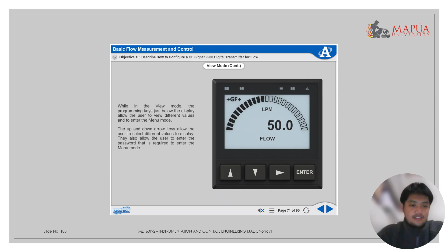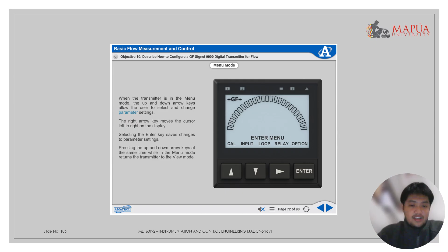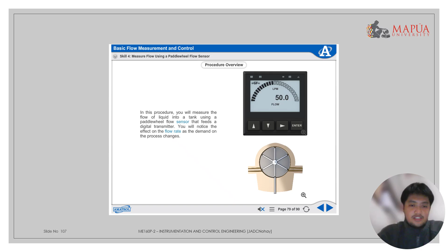When the transmitter is in the menu mode, the up and down arrow keys allow the user to select and change parameter settings. The right arrow key moves the cursor from left to right on the display. Selecting the enter key saves changes to parameter settings. Pressing the up and down arrow keys at the same time while in the menu mode returns the transmitter to the view mode. Here is the procedure overview and the review.